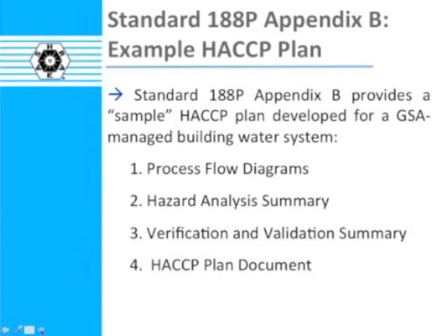If what I'm about to say sounds like semantics to you, then my recommendation is that you think more deeply about it. Risk assessment implies a quantitative determination about risk. Assessment is a quantitative word. But the risk of legionellosis cannot be quantified. And therefore, you'll see no reference to risk assessment or quantifying risk in this standard. It's a risk characterization, which is very qualitative, not quantitative. It's about hazard analysis and hazard control.